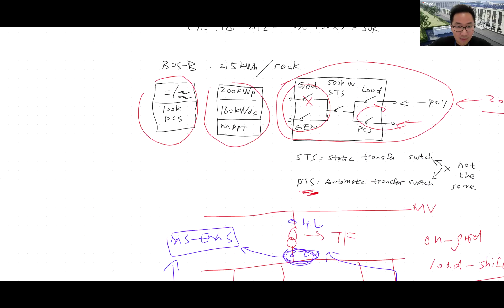People also ask about it: our 215 has what's called a black start function. Our 215 can sustain itself. It's not all due to 215, it's really thanks to the technology given to us by our good people in the inverter department. For our PCS, there are 2 main operating modes, what's called VF mode and PQ mode. VF mode is the grid forming. That's the mode the PCS will be working in during off-grid operation, in microgrid operation.